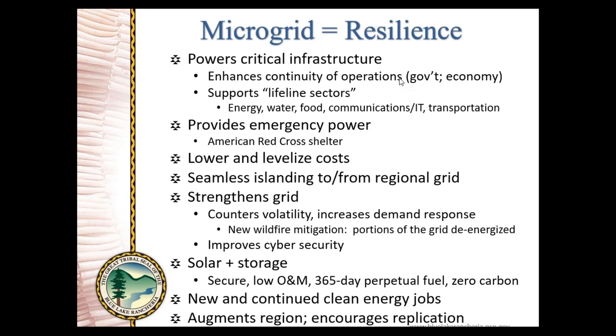The microgrid's centralized management system automatically has our rate tariff embedded in it, so it is on autopilot 99% of the time, optimizing the solar and battery storage. It's arbitraging that system to even out and reduce our energy costs, starting with the most expensive energy, which for us is between 12 and 6 p.m. every day. There are some seasonal details to that, but we have time-of-use rates, so all of that is just plugged into the system. When the rates change, and they're certain to change, we just plug in the new tariff, and the system automatically optimizes for it. That's a wonderful benefit to the system too.